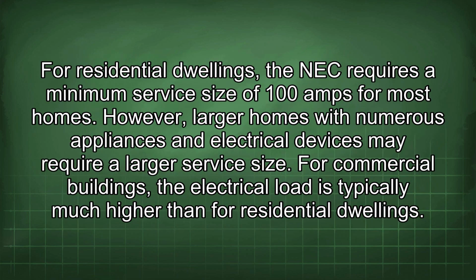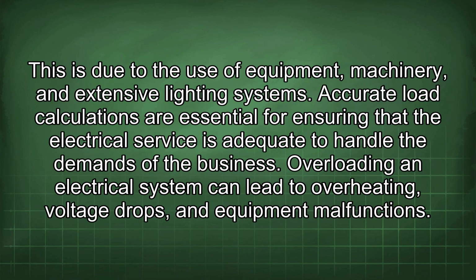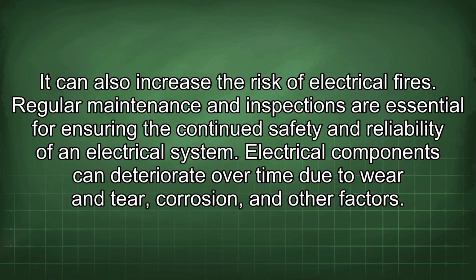For residential dwellings, the NEC requires a minimum service size of 100 amps for most homes. However, larger homes with numerous appliances and electrical devices may require a larger service size. For commercial buildings, the electrical load is typically much higher than for residential dwellings. This is due to the use of equipment, machinery, and extensive lighting systems. Accurate load calculations are essential for ensuring that the electrical service is adequate to handle the demands of the business. Overloading an electrical system can lead to overheating, voltage drops, and equipment malfunctions. It can also increase the risk of electrical fires.